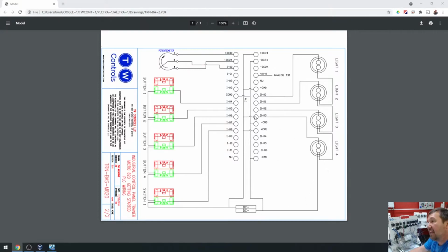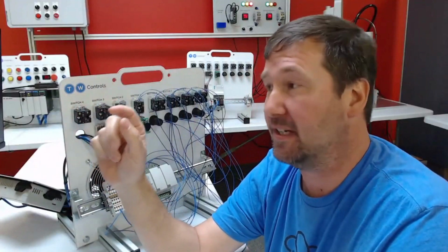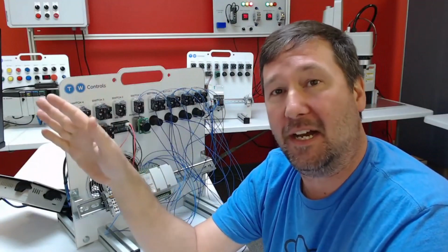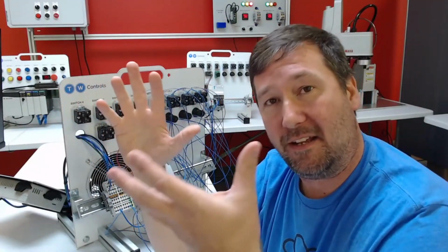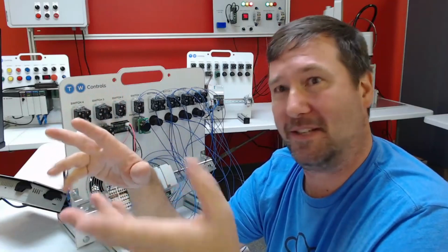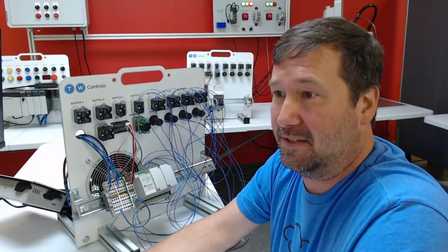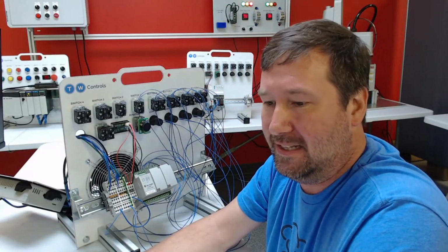And since we're at it, these are sourcing outputs. And it's really confusing, because typically if you have sinking inputs, you will have sourcing outputs. Pretty rare it doesn't work that way. So in this case, these are the source of the power, so we're sending 24 volt out of them and going to our lights. Also, Rod, you definitely want to check out that video, because what I just told you about sinking and sourcing is for Allen Bradley. It's also for many others, but there are some PLC manufacturers that do the opposite. Some of them do the opposite on just the output. And if I recall from that video, there was actually one manufacturer that swapped the terms even on their same model PLC as they go through a manual. So they are very confusing terms. That's why I always like to see a diagram, just to see how exactly we're going to do it.